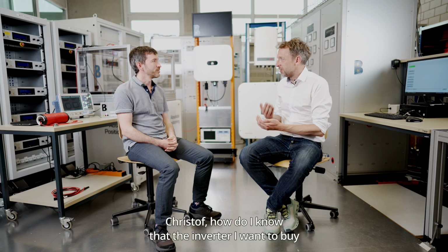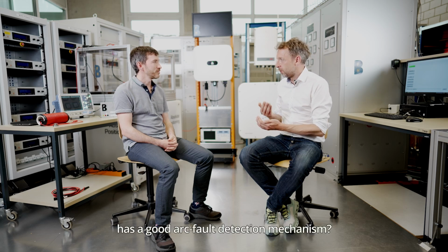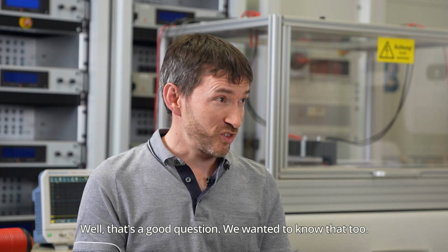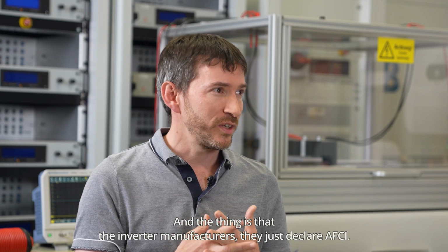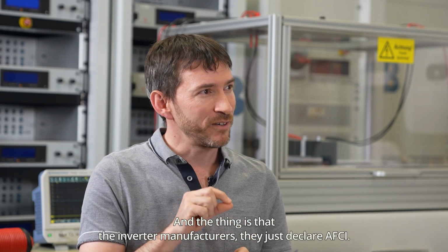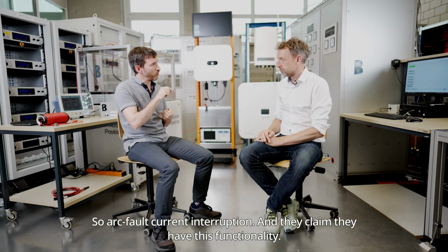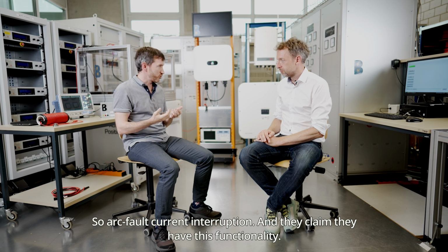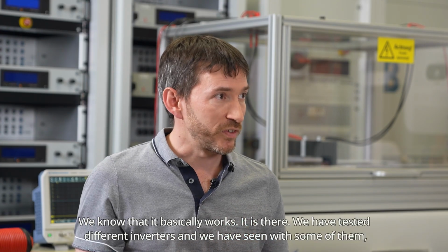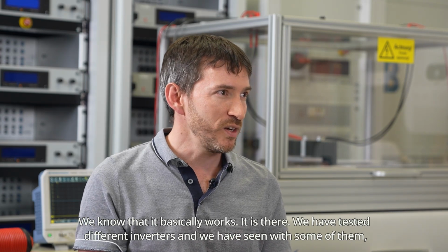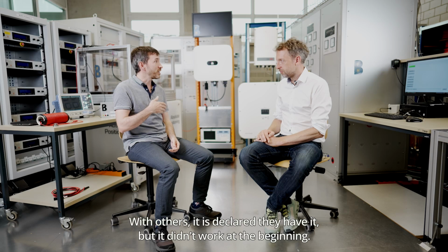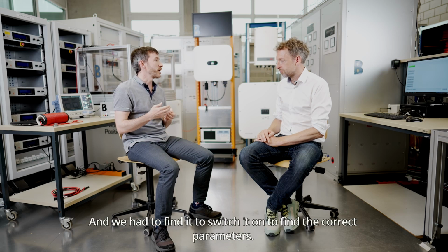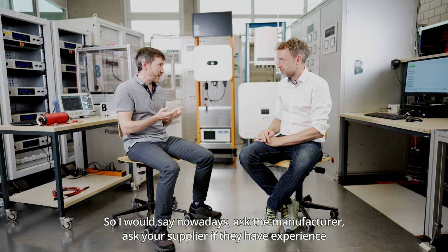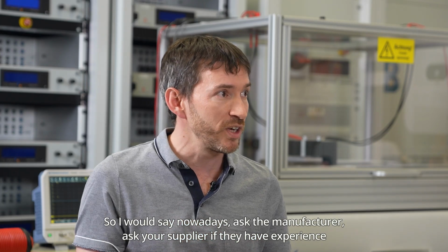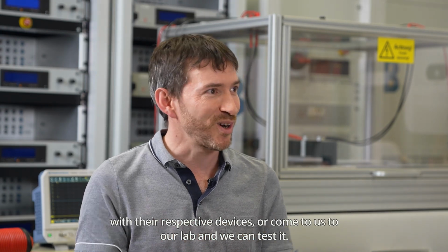Christof, how do I know that the inverter I want to buy has a good arc fault detection mechanism? Well, that's a good question. We wanted to know that too. The inverter manufacturers just declare AFCI, arc fault current interruption, and they claim they have this functionality. We know that it basically works. We have tested different inverters, and with some of them it works straight away. With others, it is declared they have it, but it didn't work at the beginning, and we had to find it, switch it on, and find the correct parameters. So nowadays, ask the manufacturer, ask your supplier if they have experience with the respective devices, or come to our lab, and we can test it.